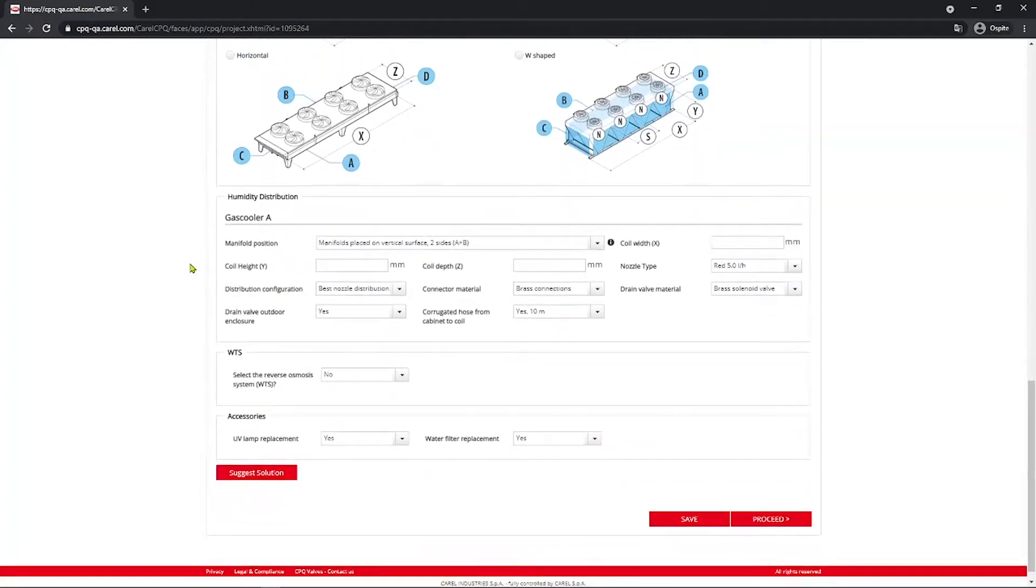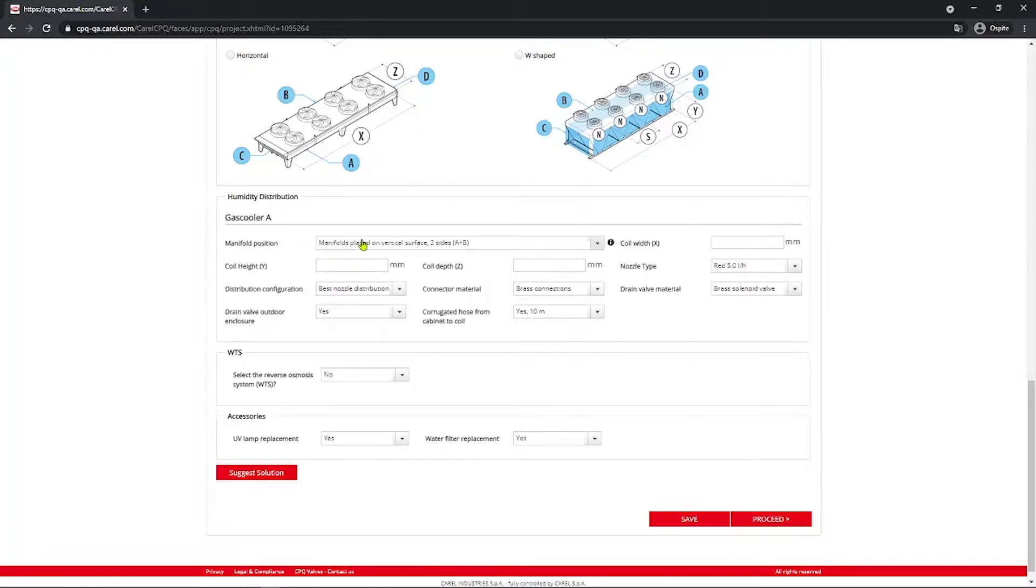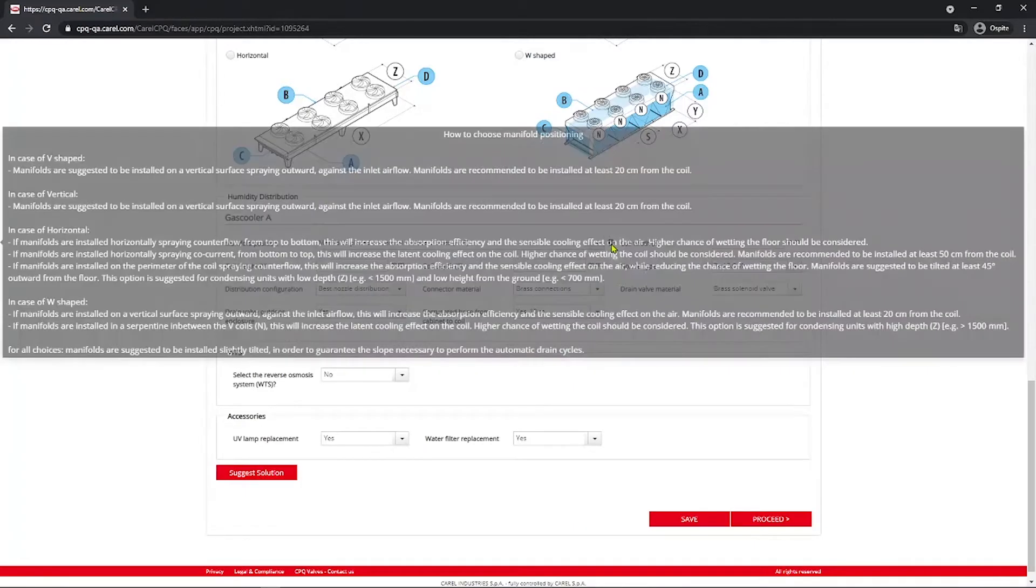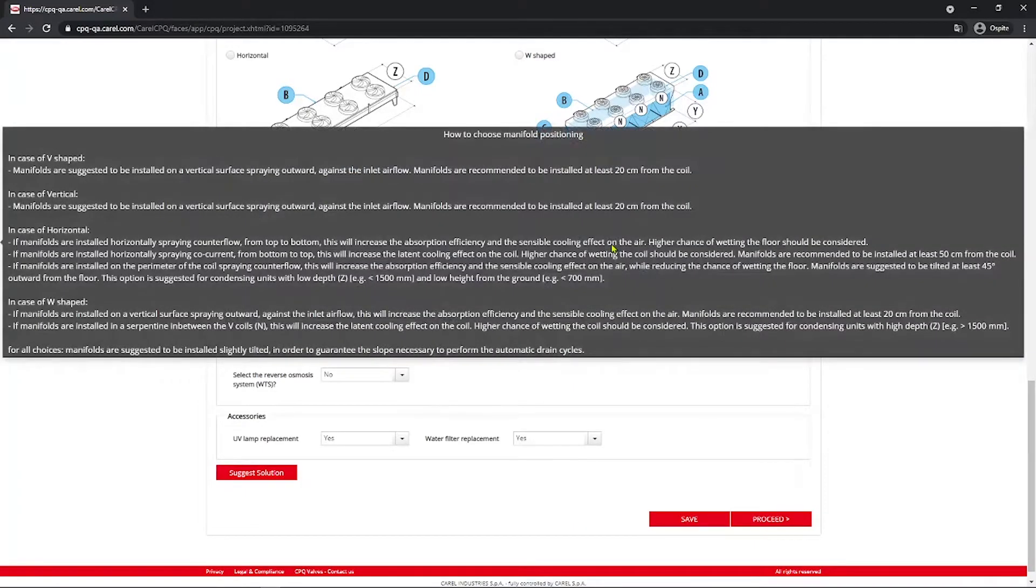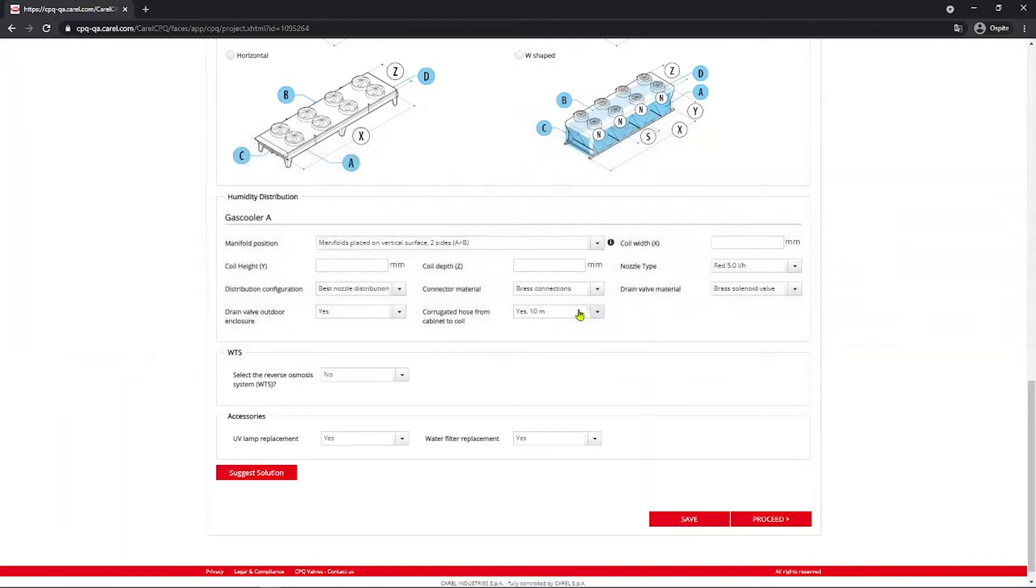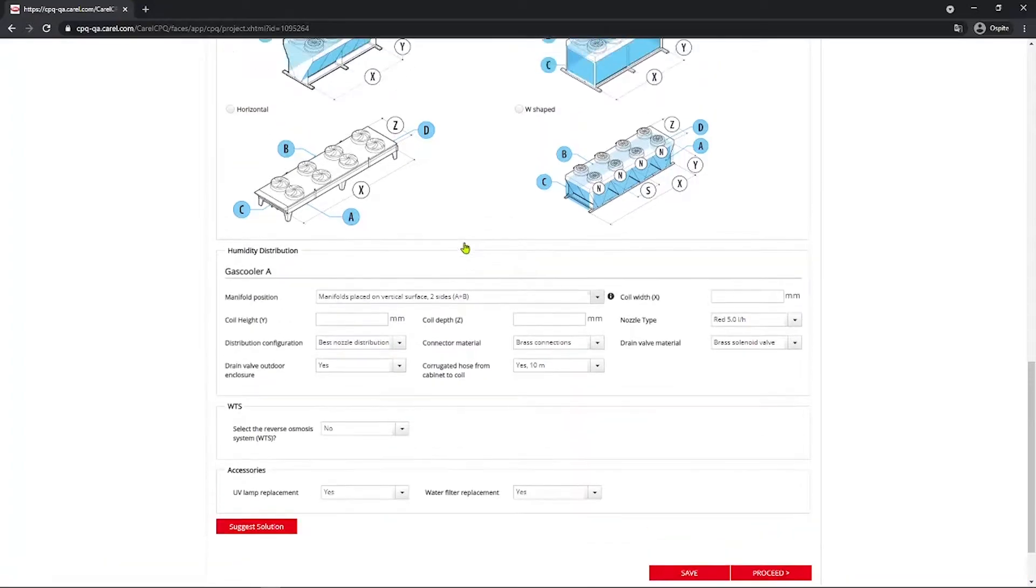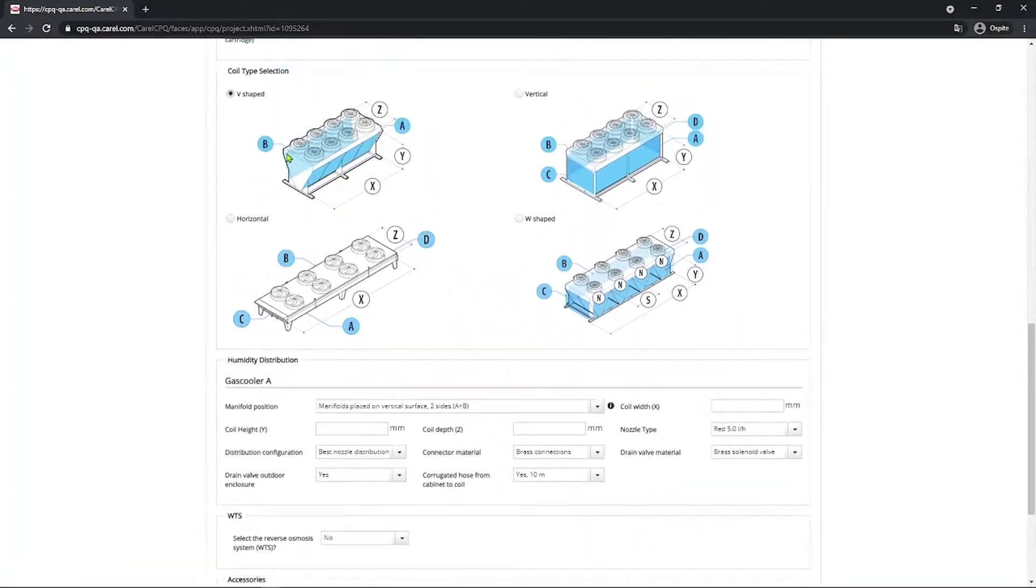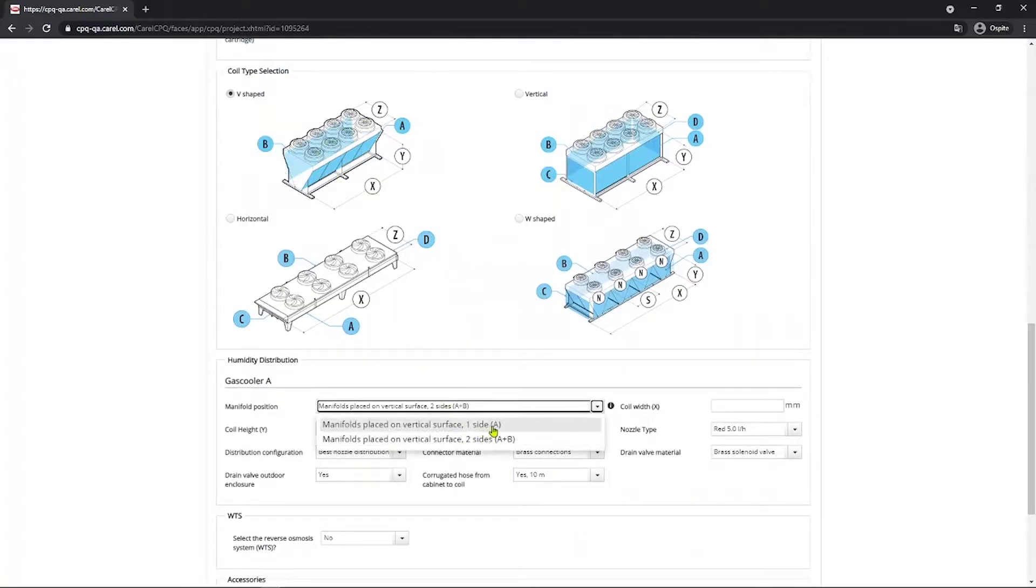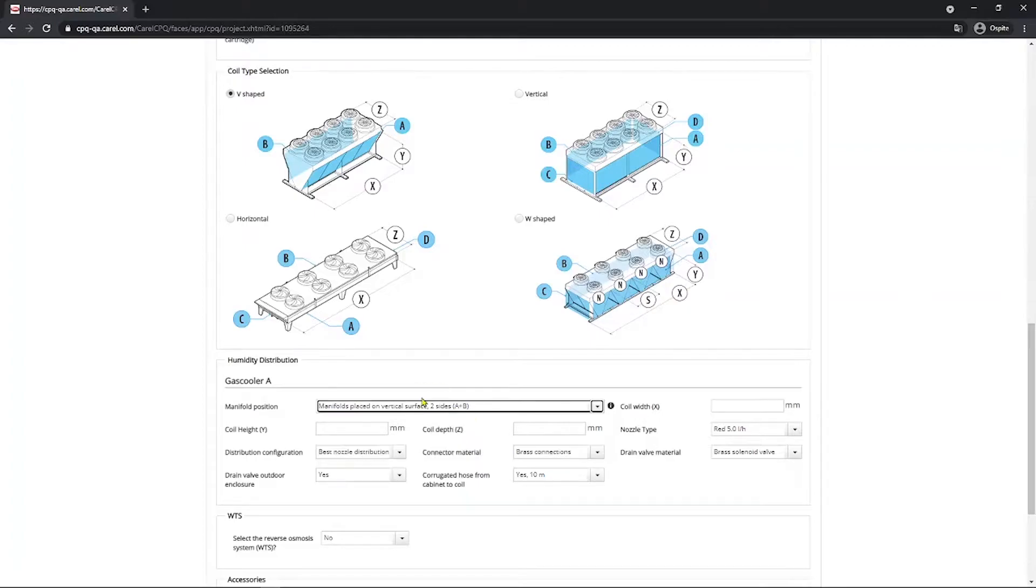Moving on, humidity distribution for gas cooler A. The manifold position here, select where the manifold will be placed on the dry cooler used for this project. This depends on a possible installation constraint and any impediments that there may be around the coil. You can see the help text here for more information. For example, you may be having a problem installing the system on both sides of the coil, so you can select just one side. Please note that the letters here, A and B, refer to the letters you find in the picture here above. If you select just one side, it's going to be just A or B, of course. For this project we select two sides A plus B.